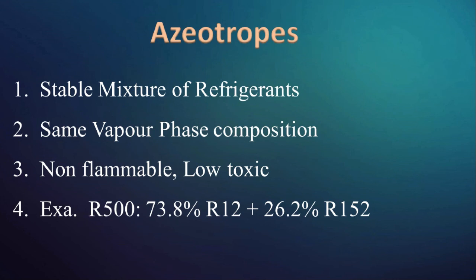Azeotropes are stable mixtures of refrigerants. Their vapor phase retains identical composition over a wide range of temperatures. They are usually non-flammable, low toxic, and non-corrosive mixtures of gas. For example, R500 is a mixture of 73.8% R12 and 26.2% R152. R500 has a fairly constant vapor pressure curve, with evaporator pressure of 1.37 bar and condenser pressure of 7.78 bar. It has a boiling point of minus 33 degree Celsius and latent heat of vaporization of 192 kJ/kg. Azeotropes find applications in commercial systems.